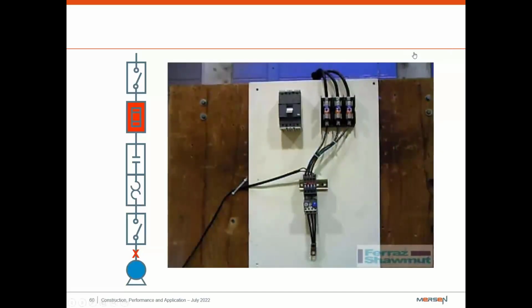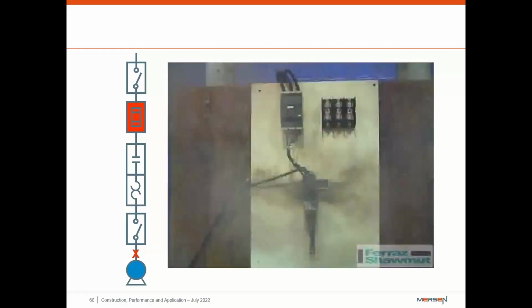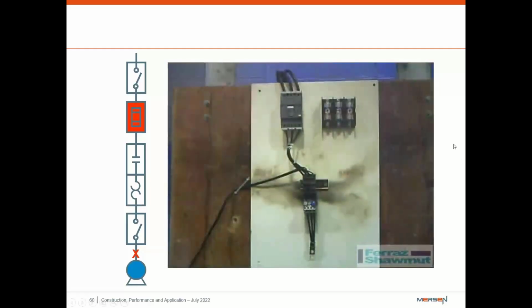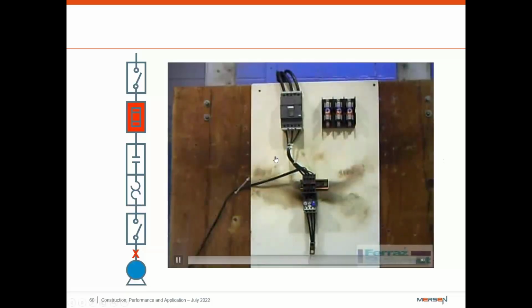As you can see, the overload relay was not damaged. The circuit was opened and there was no fault. So now we're going to go with type 1 coordination protection with a circuit breaker and a NEMA rated contactor with an overload. And again, this is a proper UL application. So down the line, the motor should be fine, but again, you're damaging equipment inside. Now this has to be replaced and fixed up.